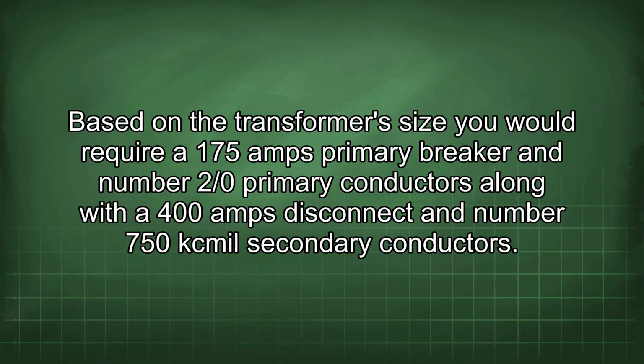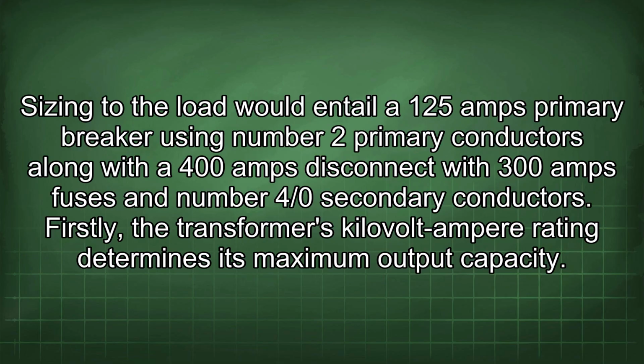Based on the transformer's size, you would require a 175 amps primary breaker and number 2/0 primary conductors along with a 400 amps disconnect and number 750 kcmil secondary conductors. Sizing to the load would entail a 125 amps primary breaker using number 2 primary conductors along with a 400 amps disconnect with 300 amps fuses and number 4/0 secondary conductors.